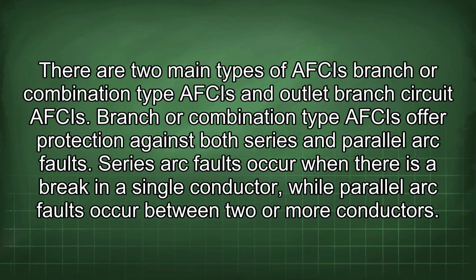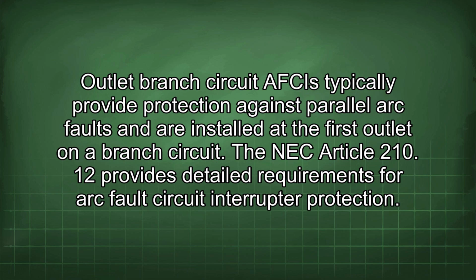There are two main types of AFCIs: branch or combination type AFCIs and outlet branch circuit AFCIs. Branch or combination type AFCIs offer protection against both series and parallel arc faults. Series arc faults occur when there is a break in a single conductor, while parallel arc faults occur between two or more conductors. Outlet branch circuit AFCIs typically provide protection against parallel arc faults and are installed at the first outlet on a branch circuit.